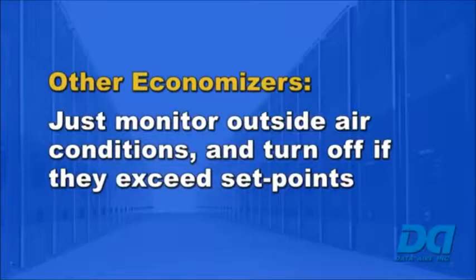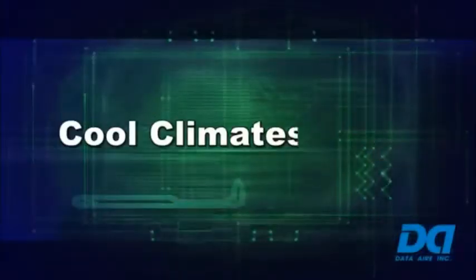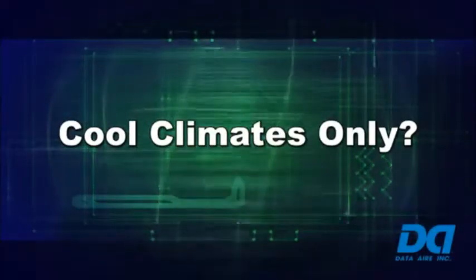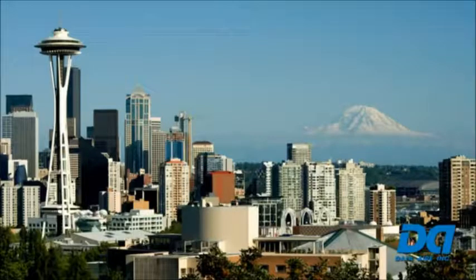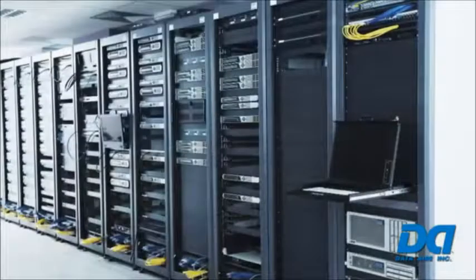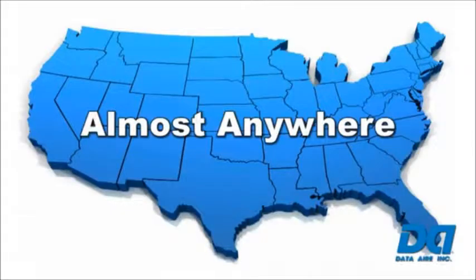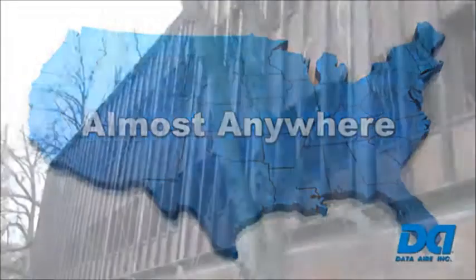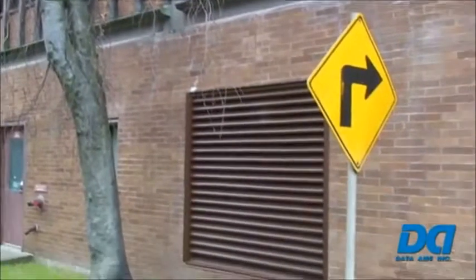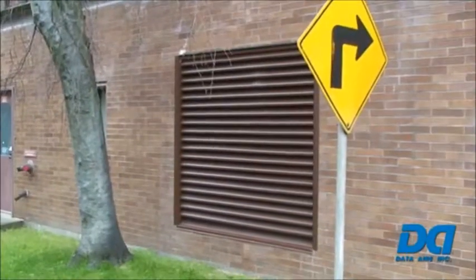Economizers by others merely monitor the outside air conditions, and when they exceed the set points, the economizer is turned off. Some feel that air economizers can only be used in cool climates, typically the northwestern United States. However, with the expanded ASHRAE temperature and humidity envelopes, data centers' year-round cooling requirements, and modulation of actuators, airside economizers can even make sense in hot and humid climates almost anywhere in the U.S. except Florida.